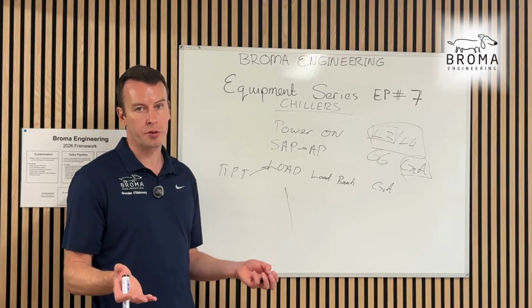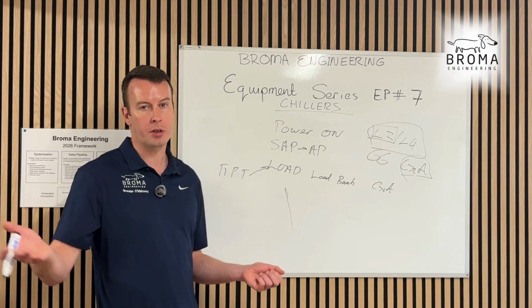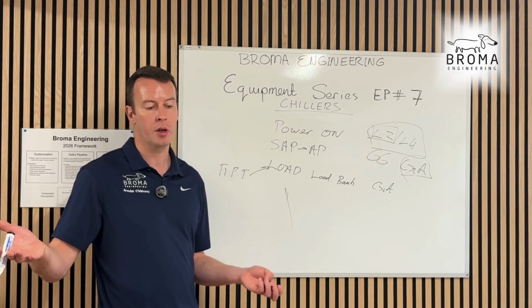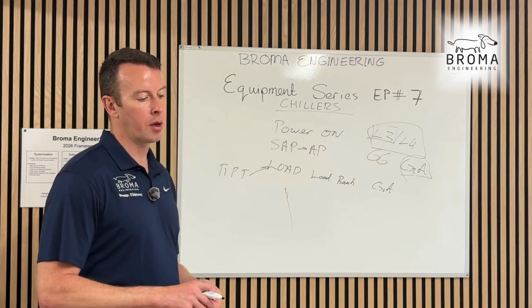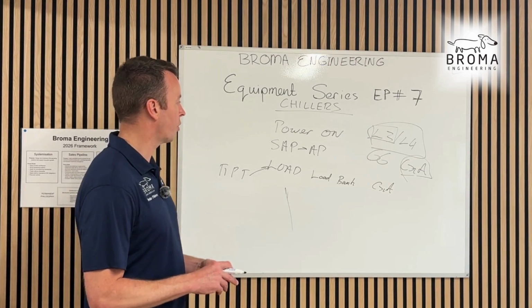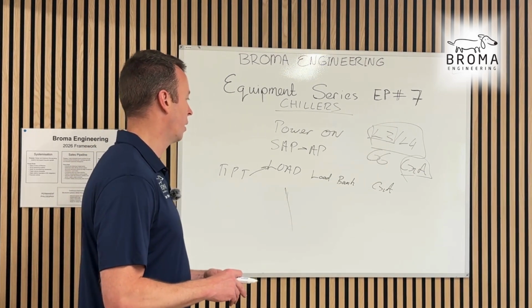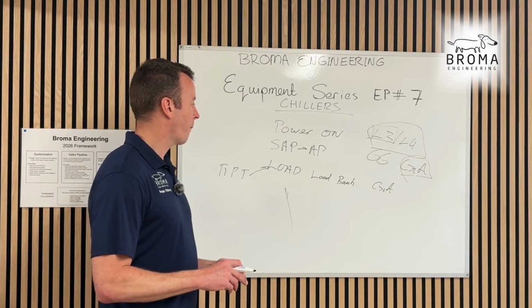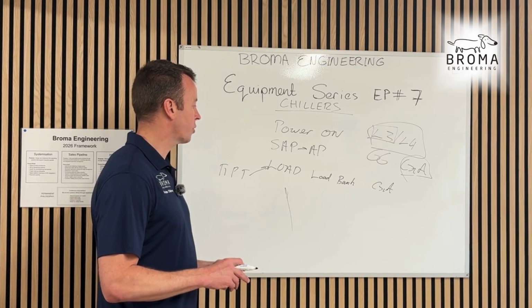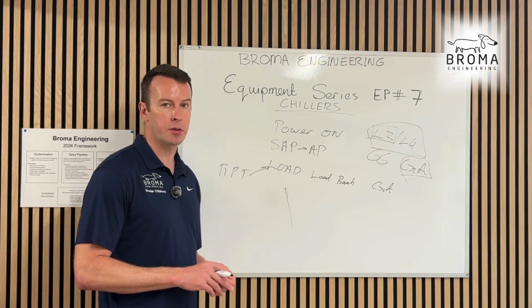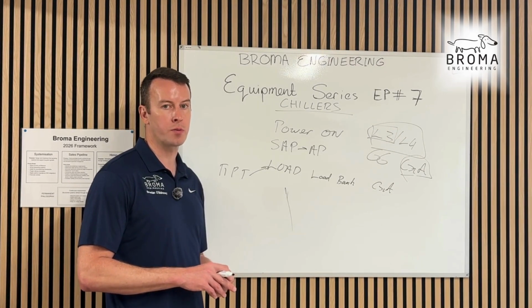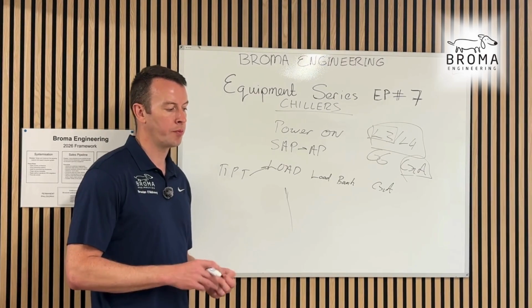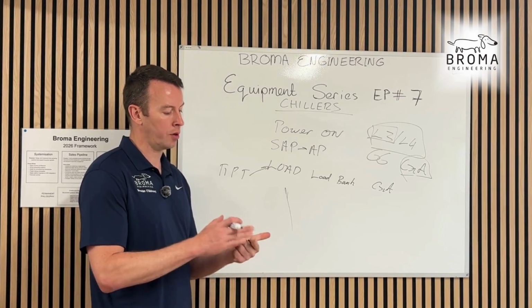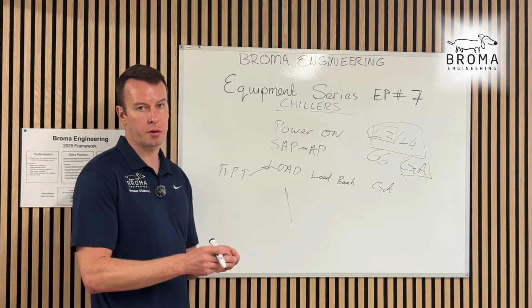Spare parts, make sure there's loads of spare parts. Either in the factory with the vendor, they can ship out quickly, or they're there on site. Things do break, things burn, things get damaged. And critical snags, make sure nobody puts up a critical snag that isn't a critical snag. A critical snag is only something that can damage people, which is very important, and equipment. Anything else is not critical.